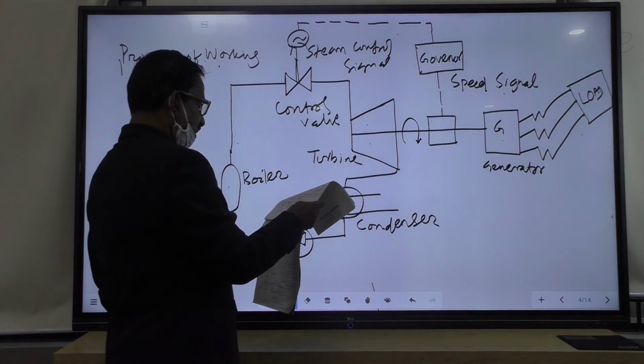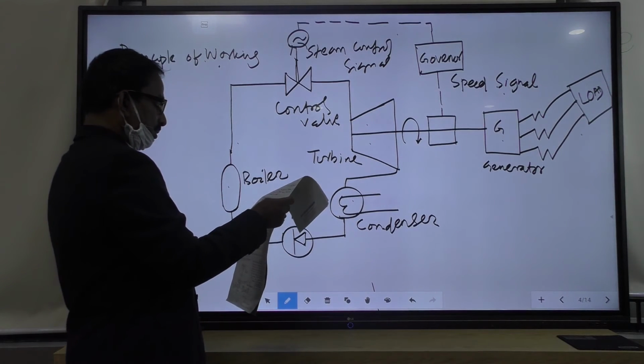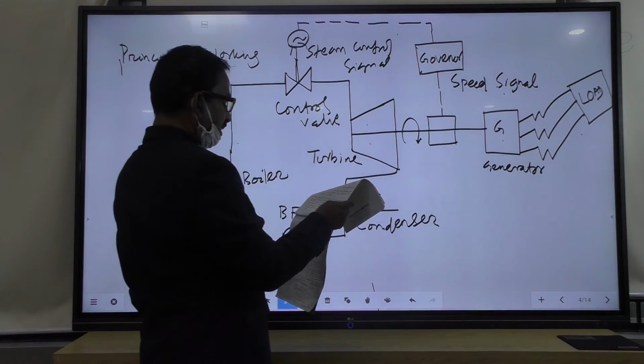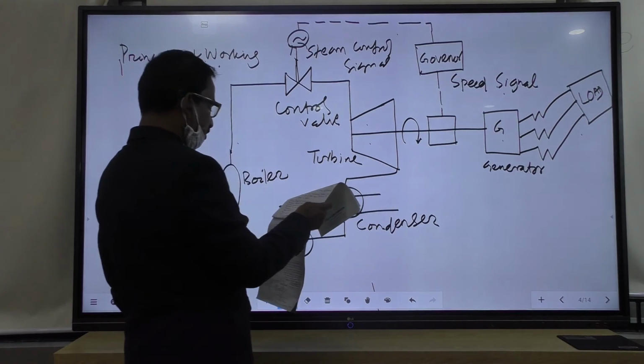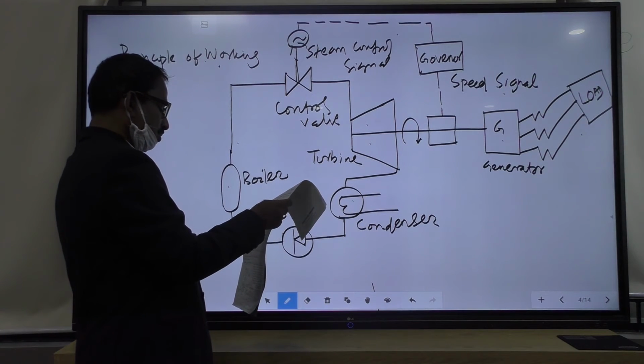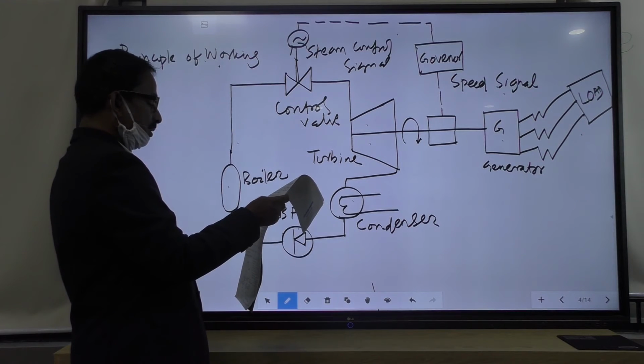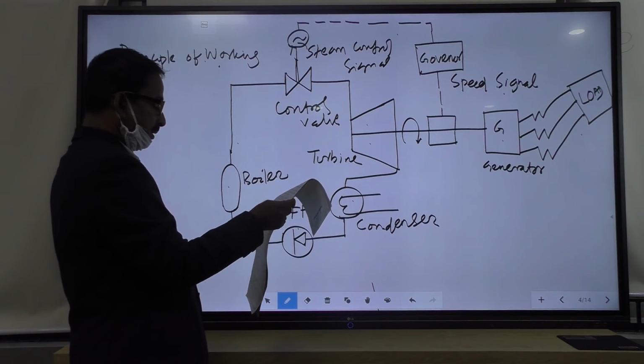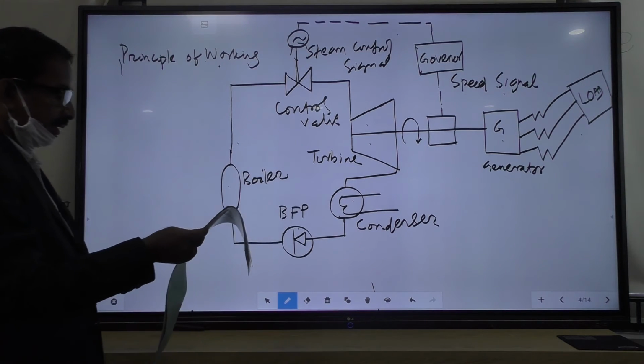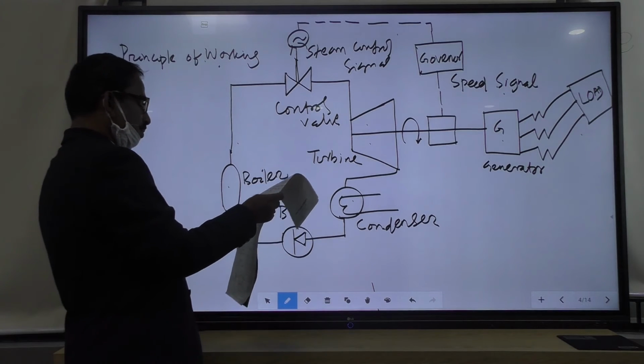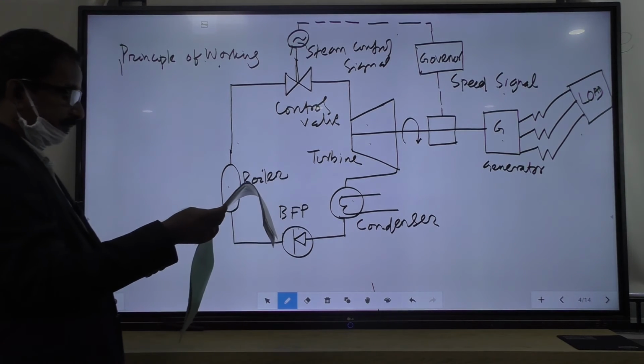Similarly, if the load is reduced, the turbine starts accelerating, and to bring the machine back to the rated speed, the steam flow to the turbine is reduced. So if the load reduces, the steam flow also reduces. Load increases, steam increases; load decreases, steam decreases.